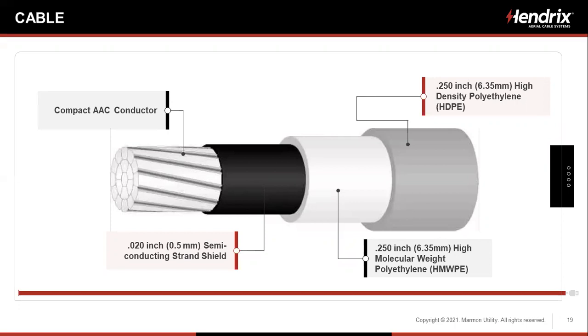So that will have benefits both for weight, for the poles, and for the guys. We're using a semi-con shield to minimize partial discharge when we are in contact with a ground plane. The middle layer there is high molecular weight polyethylene. That's a natural unfilled polyethylene. It's translucent. You can see right through it. That's going to give us a very high BIL. And it's also going to provide strippability, meaning that when I put that spiral stripping knife into the outer layer, it's going to go into the inner layer and strip quite easily. So that's quite functional as well from an operational standpoint.